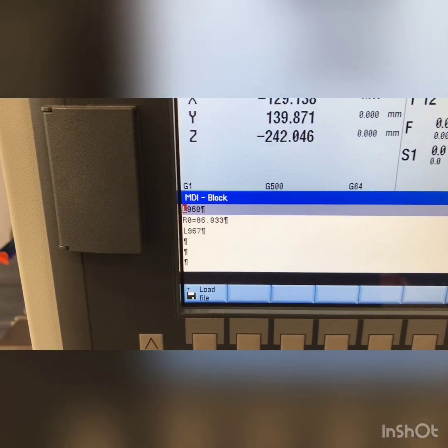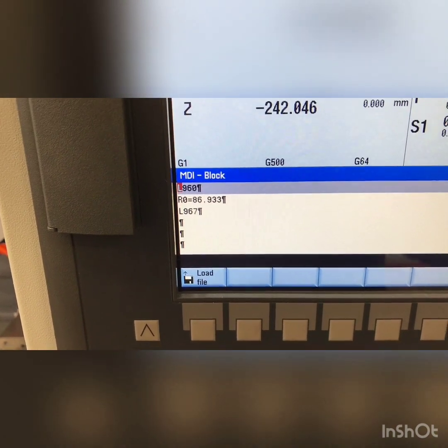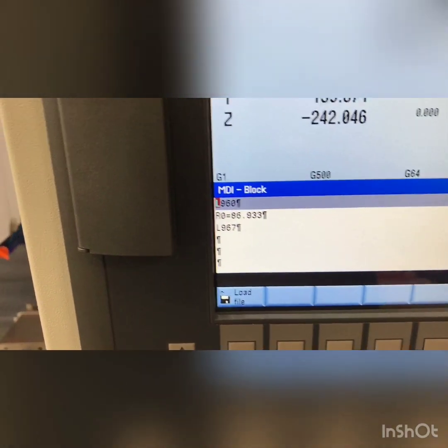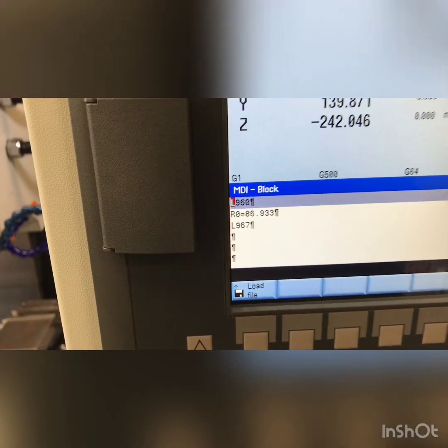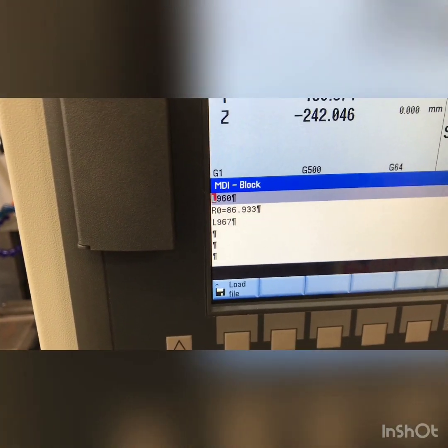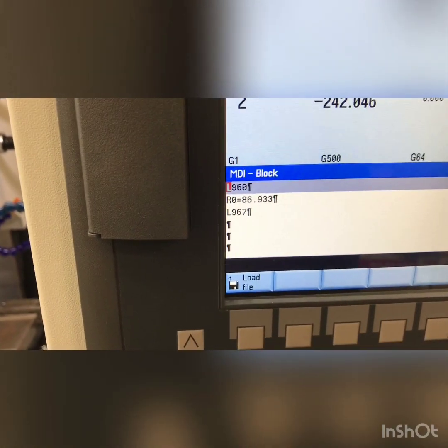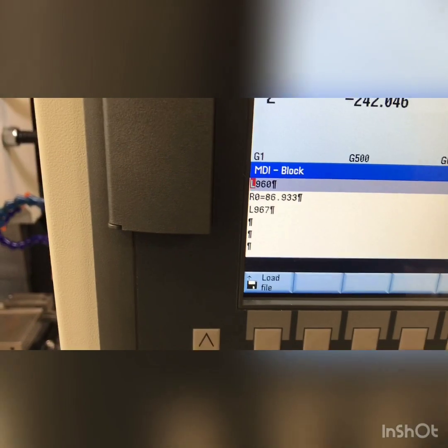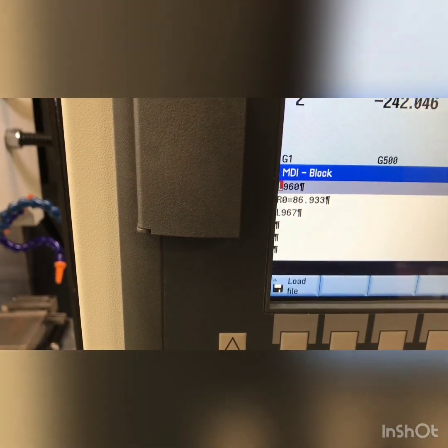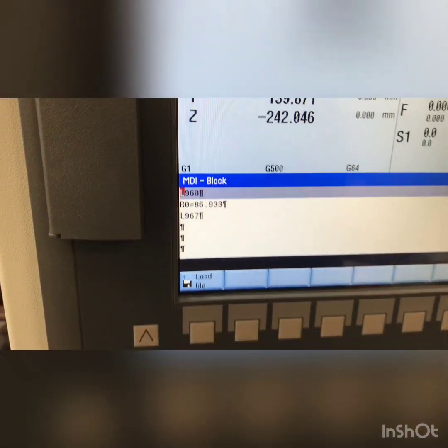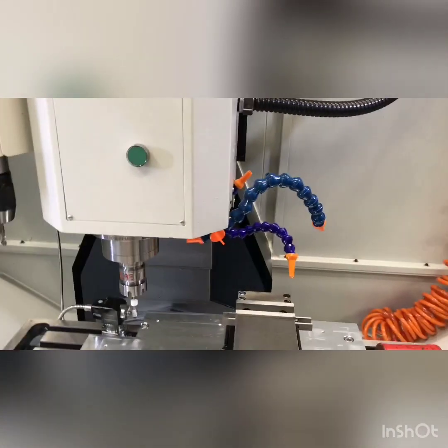So L960, that clears all the previous R values that are set in the system. R0 equals 86.933, so that is the length we measured for what they call the standard mandrel. So that's your master tool. And then L967 is this measuring cycle that will set the top of the probe. So I'll run it again here. I did just do it as a test, but we'll run it again just so you can see it.